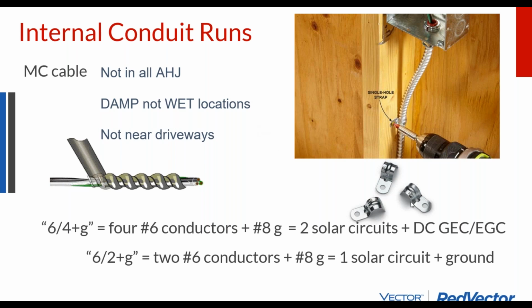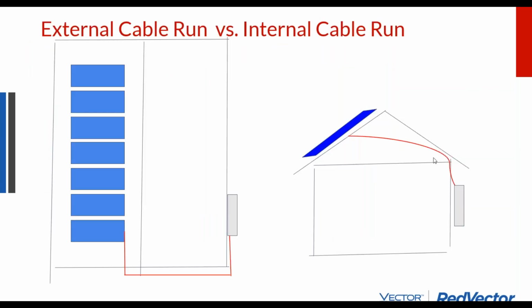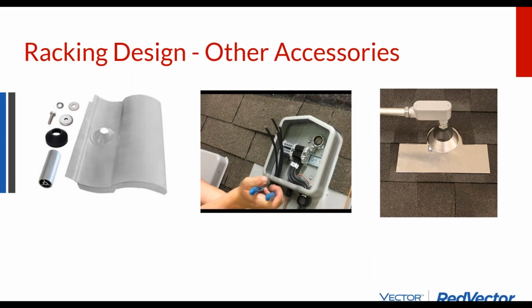The only detriment of MC cable is that it can't be installed in wet locations. It can be installed in damp locations, but what that often means is you're going to transition from MC cable to EMT. Often I'll do it right underneath the soffit, just transition to EMT and finish out the rest of my run in EMT right here. Or if it's a particularly harsh jurisdiction, I might put a box in the attic and transition to EMT in the attic itself.